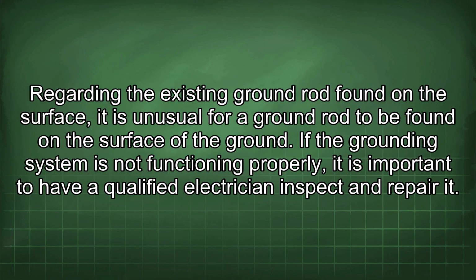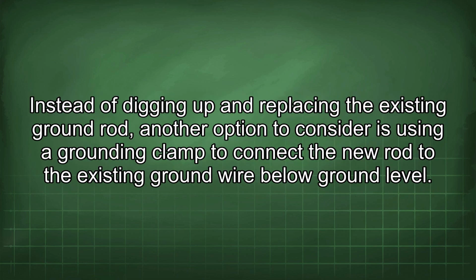Regarding the existing ground rod found on the surface, it is unusual for a ground rod to be found on the surface of the ground. If the grounding system is not functioning properly, it is important to have a qualified electrician inspect and repair it. Instead of digging up and replacing the existing ground rod, another option to consider is using a grounding clamp to connect the new rod to the existing ground wire below ground level.